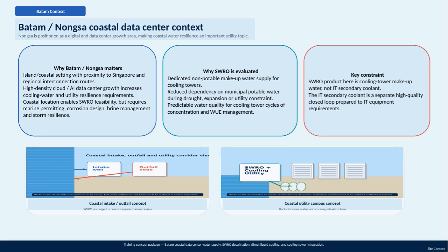Why is Batam and Nongsa so important? First, its island and coastal setting places it close to Singapore and key regional interconnection routes, which are vital for data center connectivity. The rapid growth in high-density cloud and AI data centers significantly increases the demand for reliable cooling water and overall utility resilience. Being on the coast allows us to use seawater through SWRO, but this comes with challenges like marine permits, corrosion-resistant design, managing brine discharge, and ensuring resilience against storms.